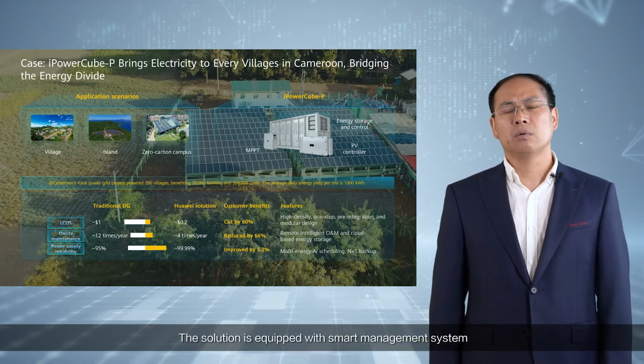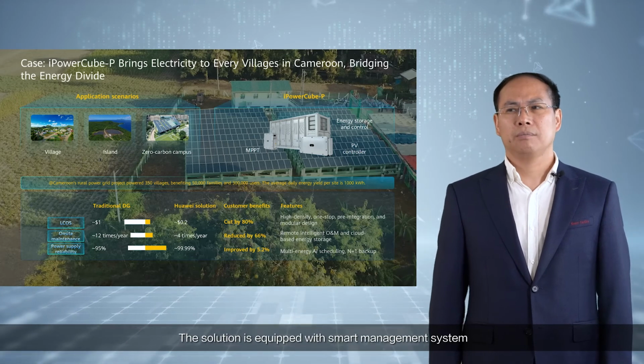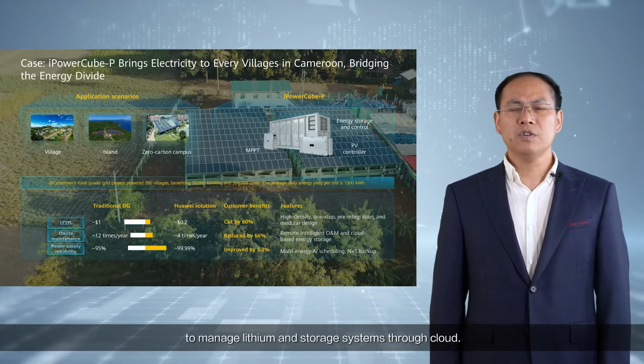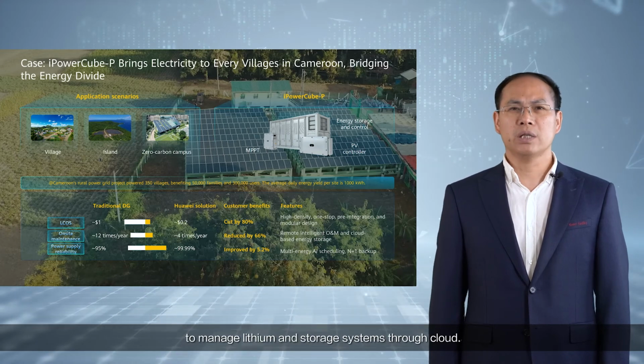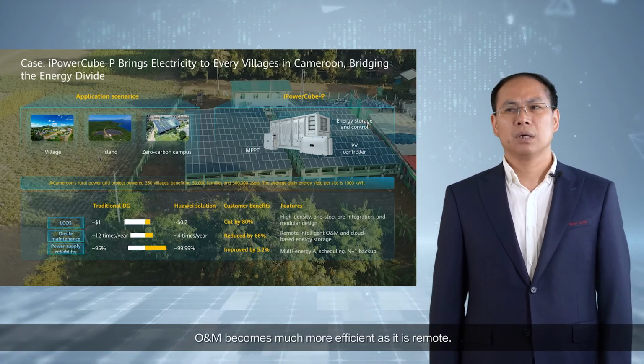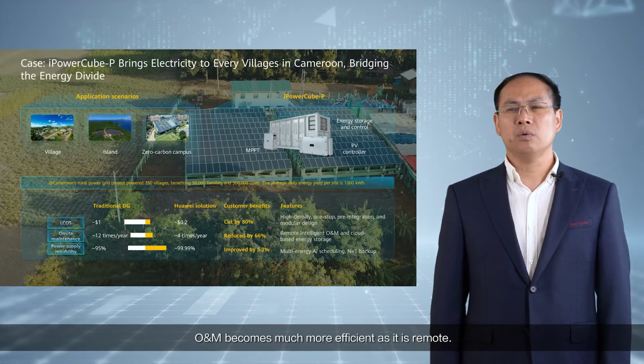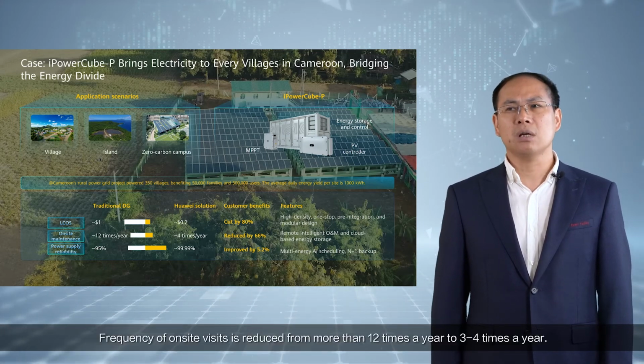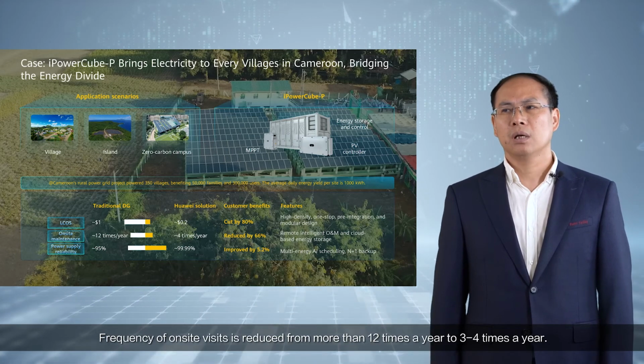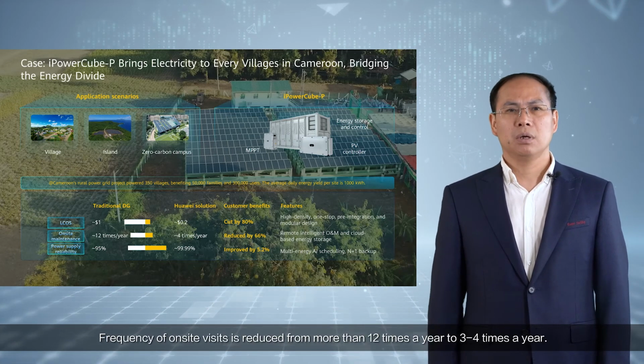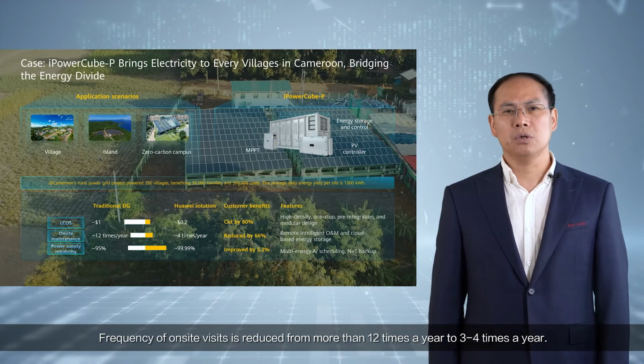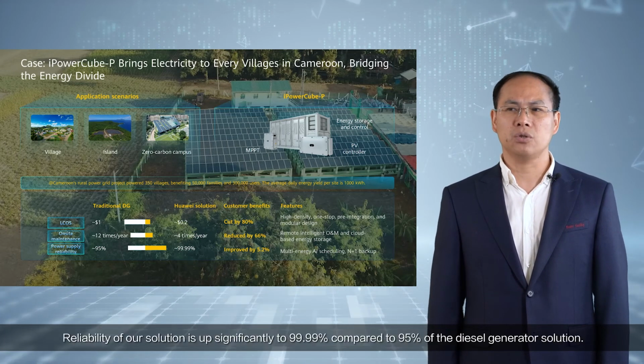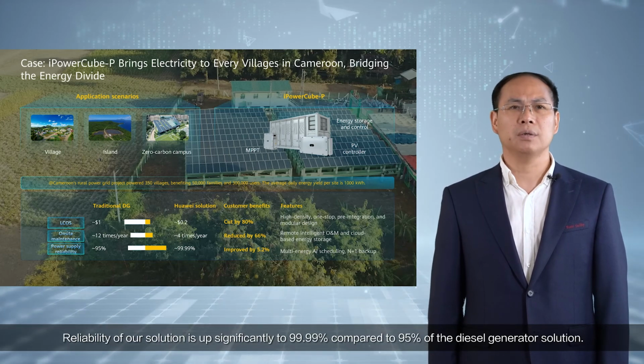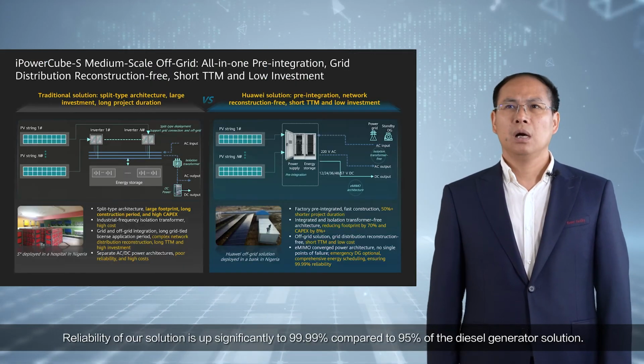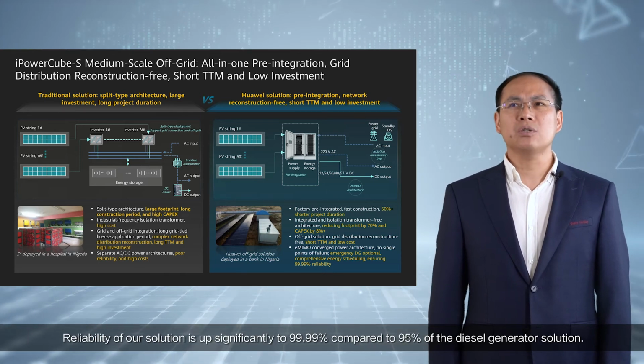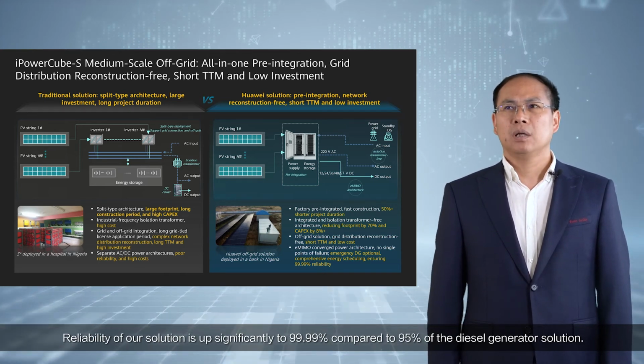The solution is equipped with a smart management system to manage lithium and storage systems through cloud. O&M becomes much more efficient as it is remote. Frequency of on-site visits is reduced from more than 12 times a year to 3 to 4 times a year. Reliability of our solution is up significantly to 99.99% compared to 95% of the diesel generator solution.